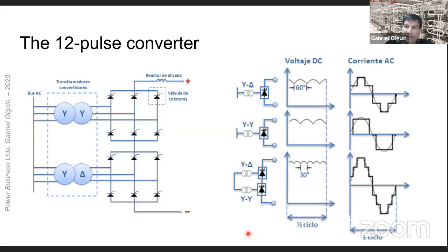Now that we understand the operating principles of the 6-pulse LCC converter, we can move to understand the 12-pulse LCC converter. The 12-pulse LCC converter is the building block of a monopolar HVDC link. This is a monopolar HVDC link. This slide shows the way a 12-pulse converter is made out of two 6-pulse converters. The phase shift introduced by the converter transformer system allows a more sinusoidal current in the AC side and a flatter current in the DC side, thus reducing the harmonic filters.